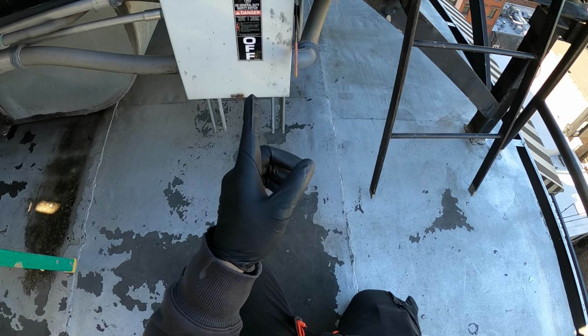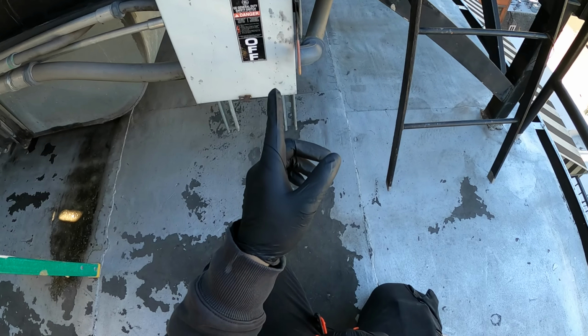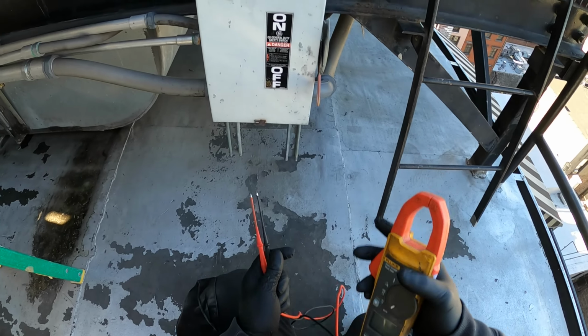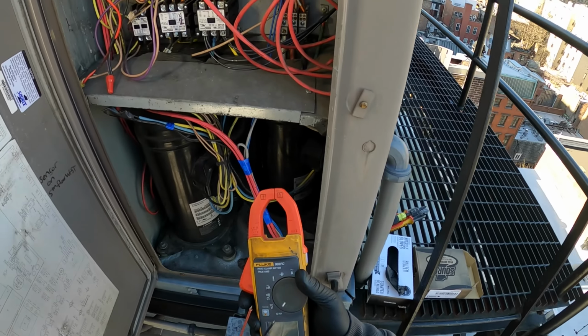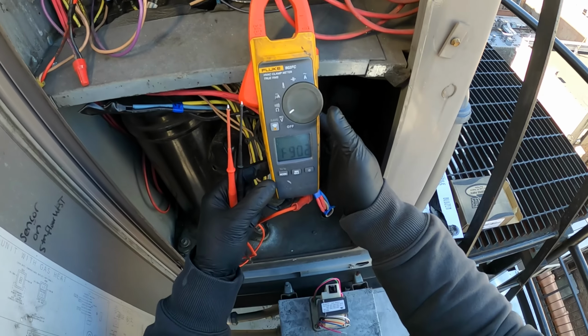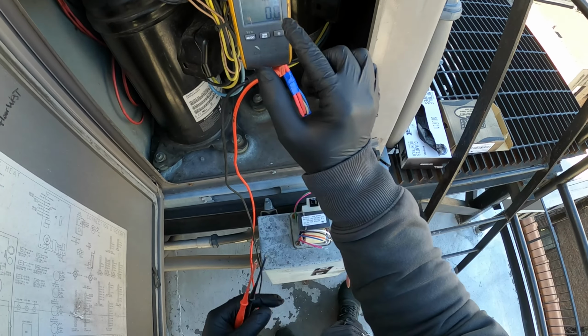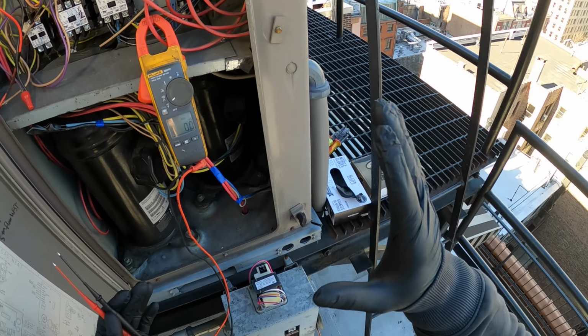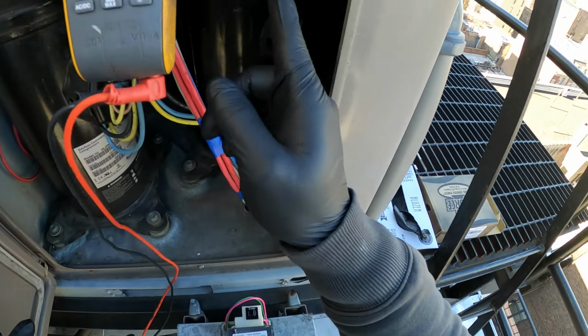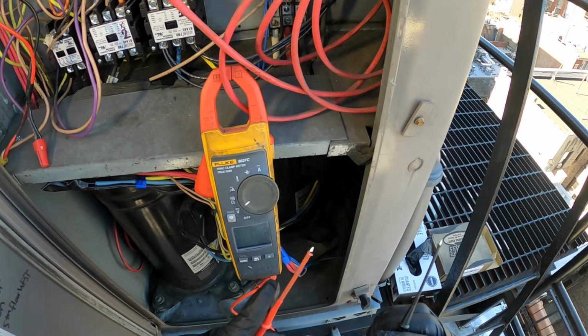First things first, make sure your power is off before doing any electrical work. Here's the disconnect, power is off, but don't always trust that. Take your meter. We're gonna set our meter to volts AC. You're gonna wanna know where the power comes in. Through here, follow those wires into that terminal block.